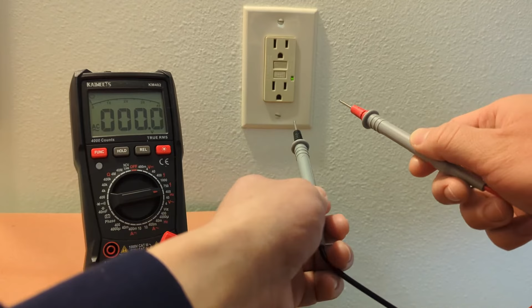Another test you can do is check the voltage on the neutral and ground slots. Insert the black probe lead into the ground slot and the red probe lead into the neutral slot. As expected, the voltage is close to zero, since you're not connected to the hot slot.